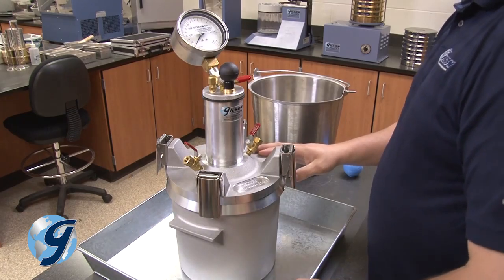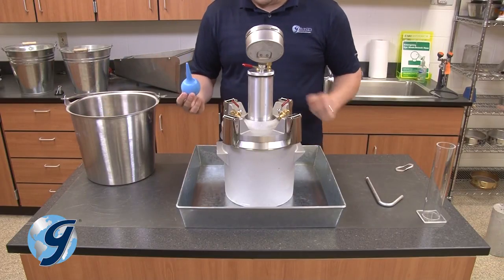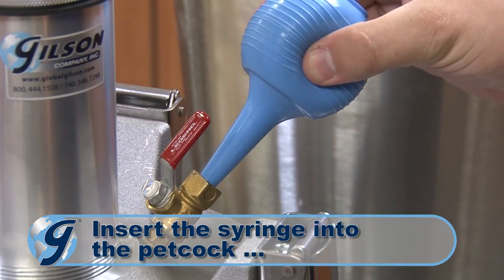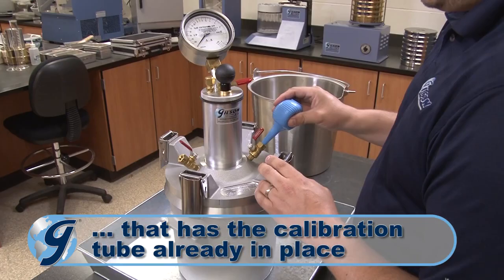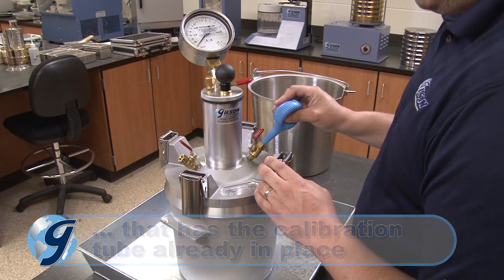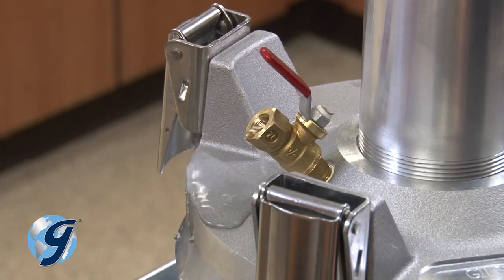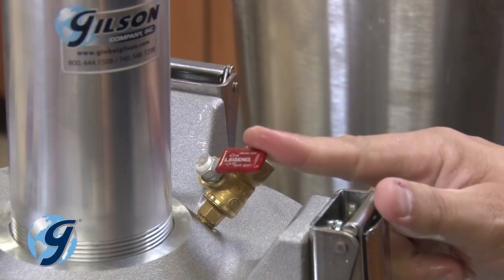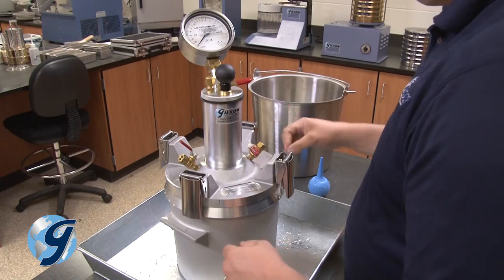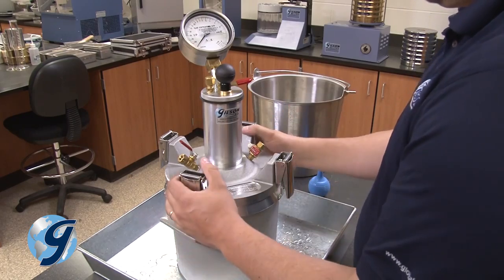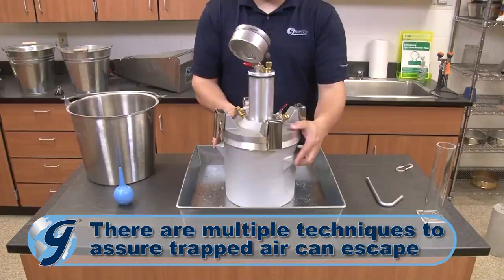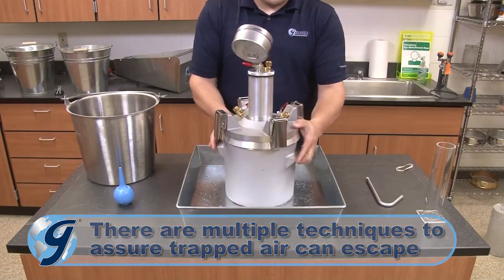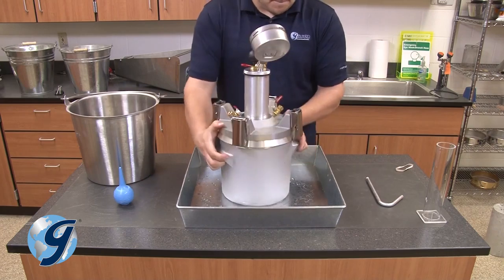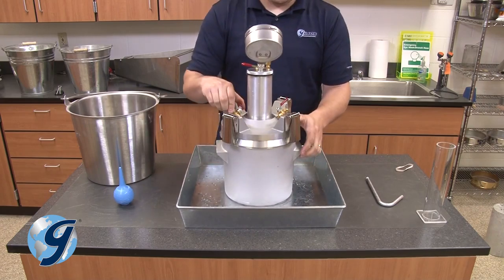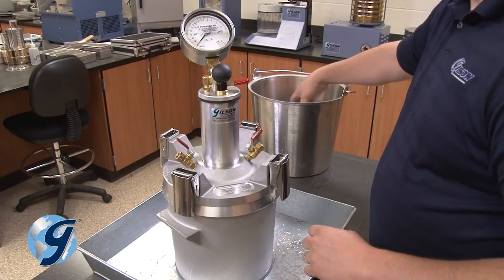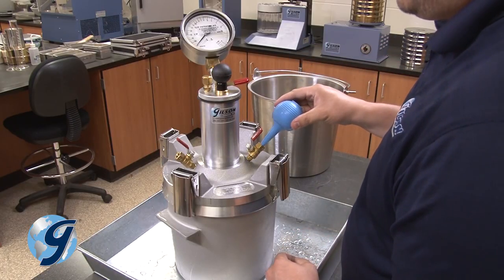To fill the air meter base with water, fill the blue syringe with water from the water bucket and place the end of the syringe into the petcock with the straight calibration tube attached to it. The base is full when water flows out the opposite petcock. Next, close the petcock that the water was injected into, leaving the other petcock open. Move the unit in such a manner so that any air still trapped in the base has a chance to escape. Now, refill any water that's been lost by reopening the petcock and using the syringe to add more water into the same petcock as previously performed.